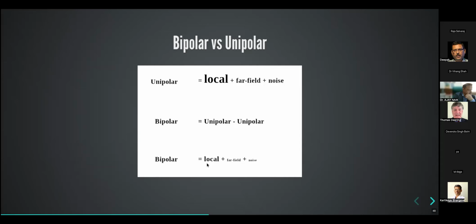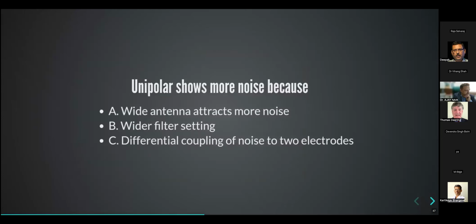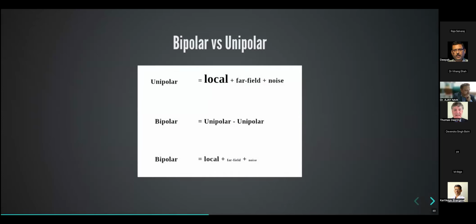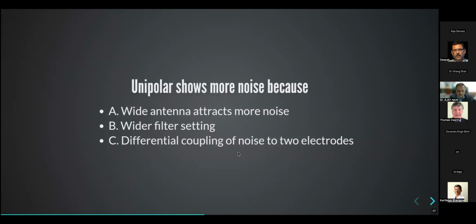Whereas any local differences, so there is a small timing difference between activation happening at the two electrodes, it is these local differences which get amplified, so that the bipolar is very sensitive to local events and very insensitive to far field events. And the reason why noise is very less on a bipolar compared to unipolar is that noise is coupled to both the electrodes equally, which means that both the electrodes see noise equally. Whereas in a unipolar, one electrode is sitting there, one electrode is a reference electrode, so that noise is differentially coupled to the two recording electrodes.